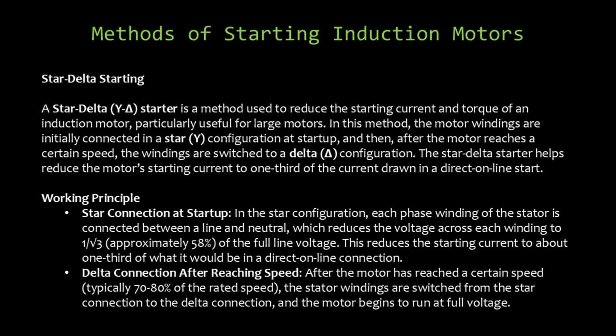Enter the star-delta starting method, a sophisticated approach to motor startup. This technique reduces starting current and torque, particularly useful for larger motors. Initially, motor windings are connected in a star configuration, then switched to delta once the motor reaches a certain speed. The star connection reduces voltage across each winding to approximately 58% of full line voltage, effectively cutting the starting current to 1/3 of a direct online start.